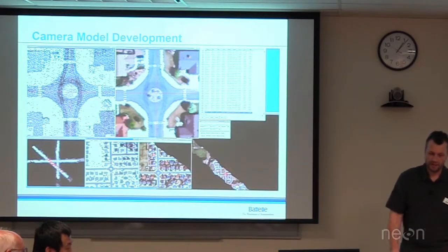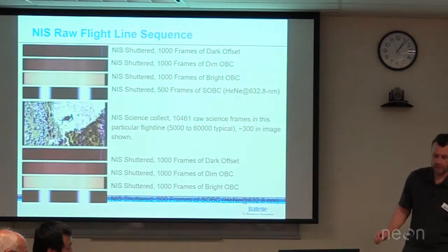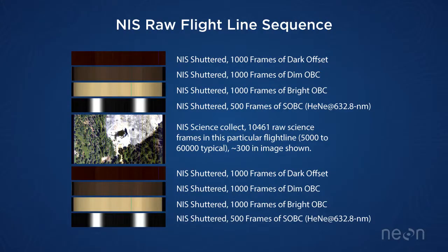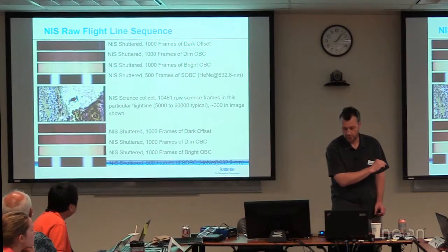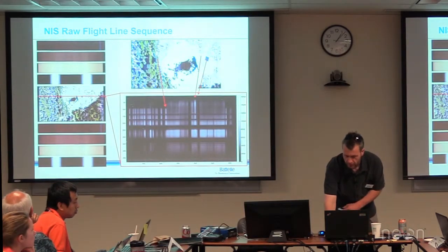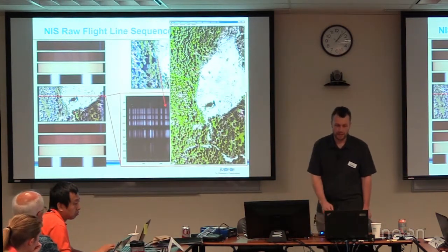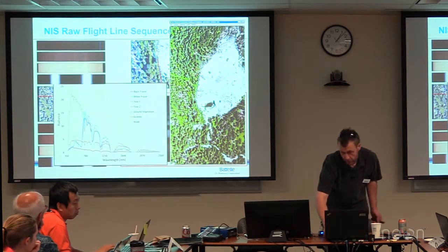This is our typical flight line collect. I want to re-emphasize that we use this data in our processing workflow, and it's vital that it's collected before and after every flight line so we understand the changes of the sensor from the lab out to when we're doing the science collects. We have both an image frame and a processed radiance image that comes from that raw data set with associated spectra.